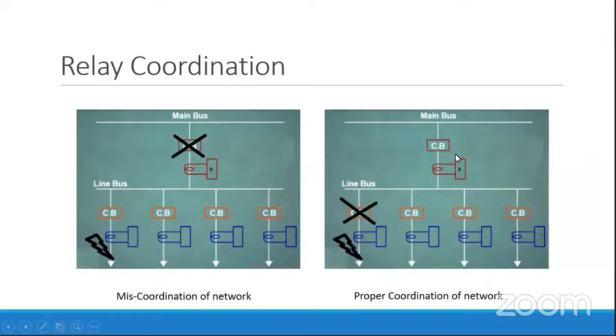So the protection should be done in such a way that the feeder at which the fault occurs should operate first. But if the fault still exists in the system, then and only then the incomer feeder should operate. So protection coordination should be done in such a way only.